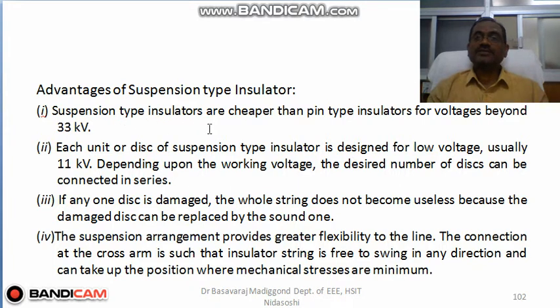The suspension type insulators are cheaper than pin type insulators for voltages beyond 33 kilovolts. If the voltage is less than 33 kilovolts, we prefer pin insulators. But if the voltage is beyond 33 kilovolts, which is obvious when we are transmitting power at high voltage, we prefer suspension type insulators. Each unit or disc of suspension type insulator is designed for low voltage, usually 11 kilovolts. Depending upon the working voltage, the desired number of discs can be connected in series.